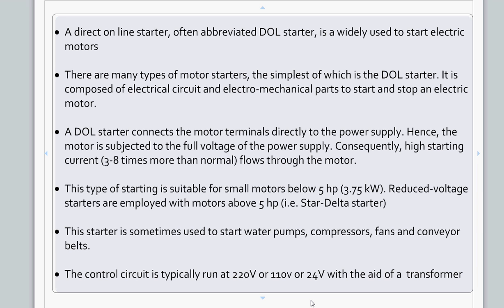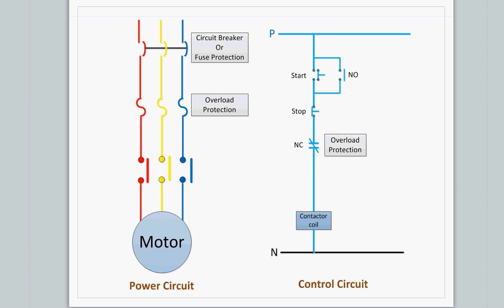This shows the power and control circuit of the DOL starter. Basically, it gets three-phase power, and a circuit breaker or fuse can be used for protection in case of motor failure or short circuit. Then there is overload protection here, and these are the contacts of the contactor. As said earlier, all three-phase voltages apply to the motor directly.